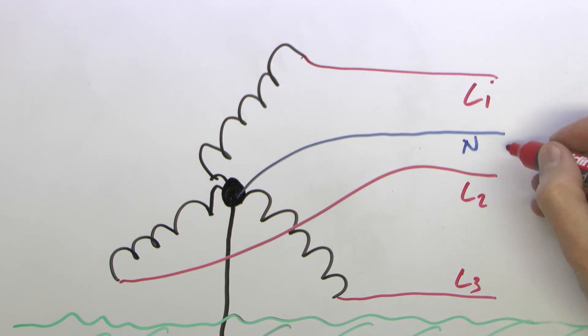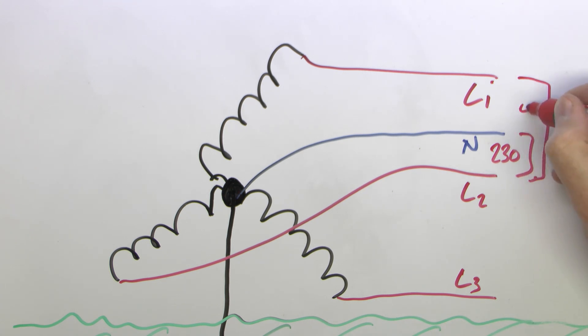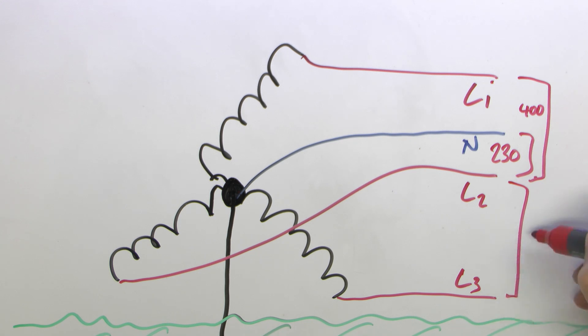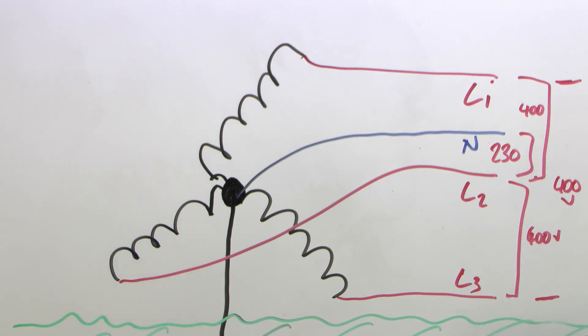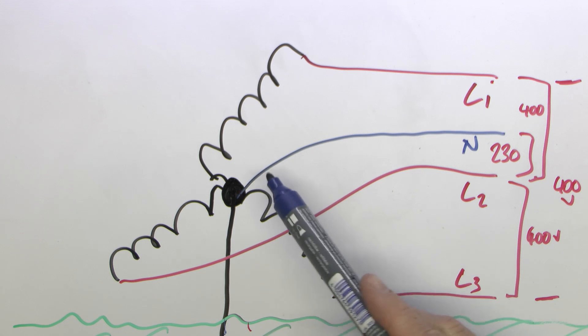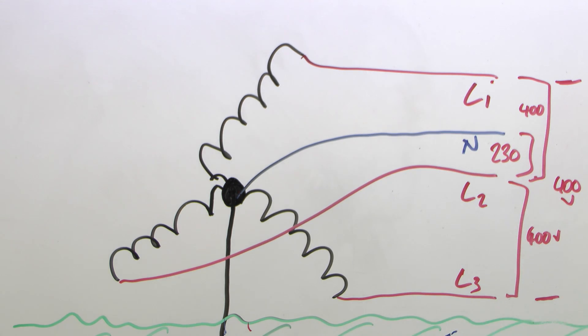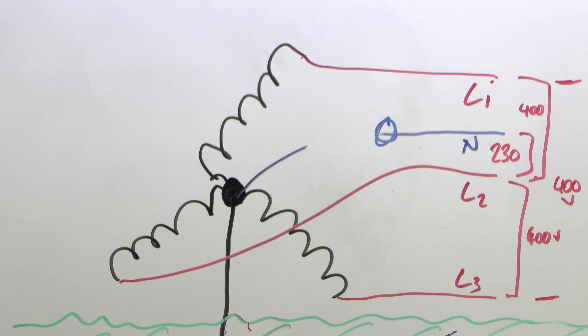For a reason I'm not going to cover in this video: although you have 230 volts between any phase and neutral, if you go between any two of the phases — say L1 and L2 — you actually get 400 volts. And the same between L2 and L3, and between L1 and L3. The reason is that these phases are not all the same — they're shifted out of phase with each other, so you get a higher voltage between any two of them. We'll cover that in another video. In terms of the neutral it's the same arrangement: it's at the same voltage as the ground simply because we've chosen to connect that particular point to the actual ground. And as long as it remains connected, the voltage between the neutral and the ground will effectively be zero most of the time. But as before, if this becomes damaged or broken, then the neutral is definitely not safe — dangerous voltages will appear.